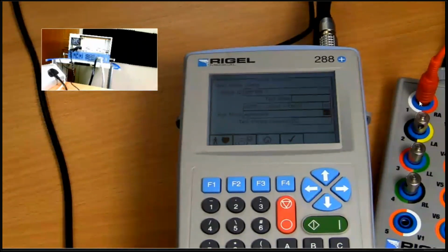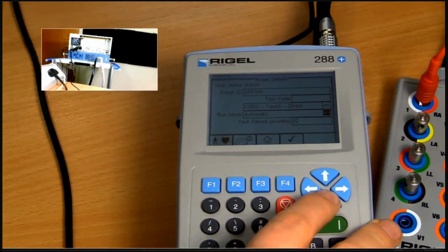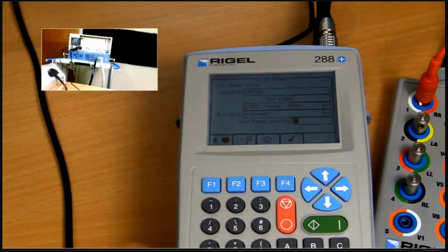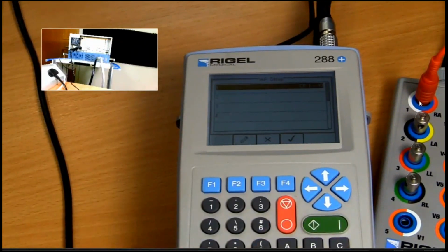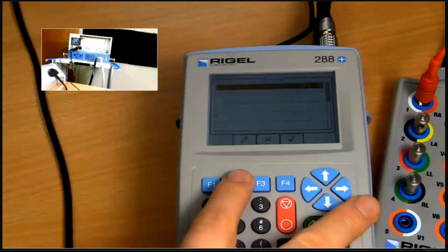Sometimes we need to power the device and leave the device powered before it'll run the operating system, and the device is being powered. So we give people options on how they prefer to test or measure leakage current by doing that. Then we have our testing period. I'm going to just keep that as default 12. But we have to press F1 because we want to determine our classification.